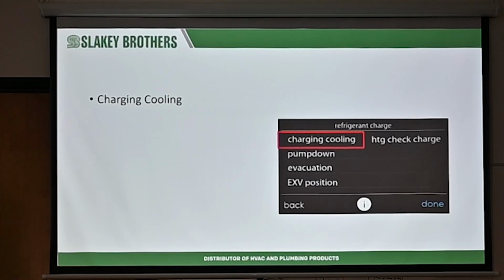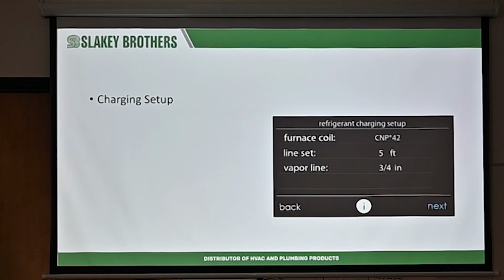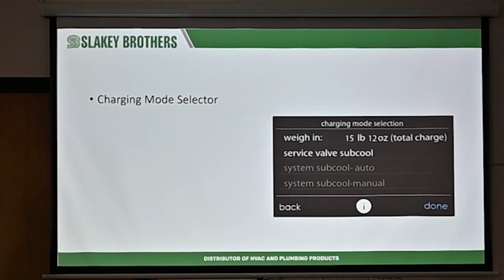So once you select that, you can do charging by cooling, heating check charge. Again, this is where you should have already put what furnace, what coil you have. You're going to tell it the line set length, the suction line size, so it tells you how much total charge they have. So this right here, total charge, this means this much refrigerant along with what came with the condenser. Okay? Then you can actually select check the subcool on the unit.